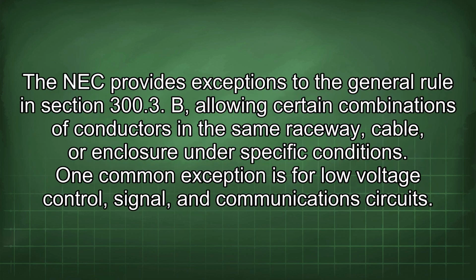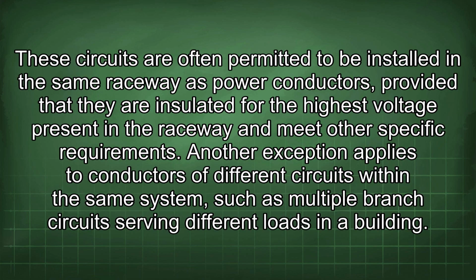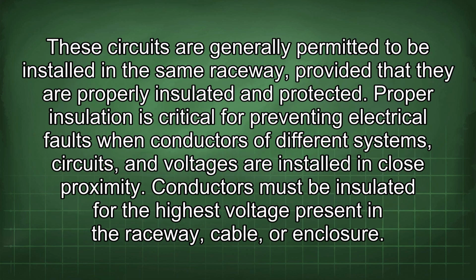The NEC provides exceptions to the general rule in Section 300.3 B, allowing certain combinations of conductors in the same raceway, cable, or enclosure under specific conditions. One common exception is for low-voltage control, signal, and communications circuits. These circuits are often permitted to be installed in the same raceway as power conductors, provided that they are insulated for the highest voltage present in the raceway and meet other specific requirements. Another exception applies to conductors of different circuits within the same system, such as multiple branch circuits serving different loads in a building. These circuits are generally permitted to be installed in the same raceway, provided that they are properly insulated and protected.